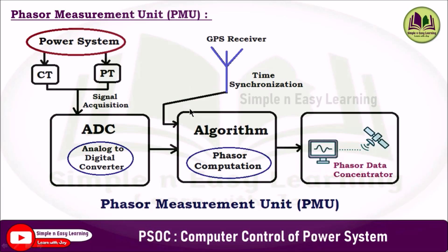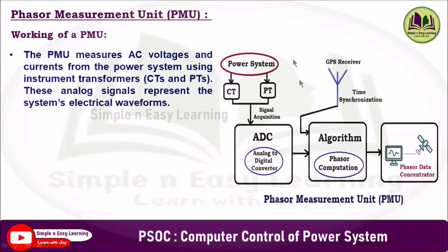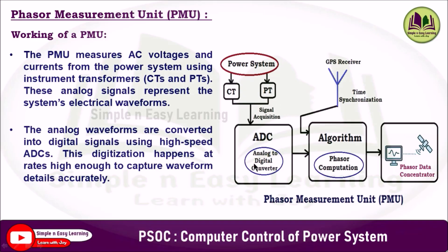The phasor measurement unit measures AC voltage and current from the power system using instrument transformers such as CT and PT. These analog signals represent the system's electrical waveform. The analog waveforms are converted into digital signals using a high-speed ADC, and this digitization happens at rates high enough to capture waveform details accurately.